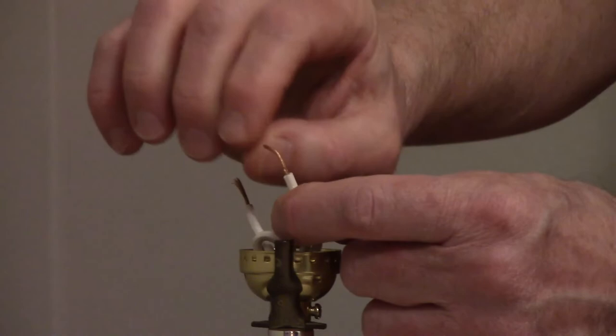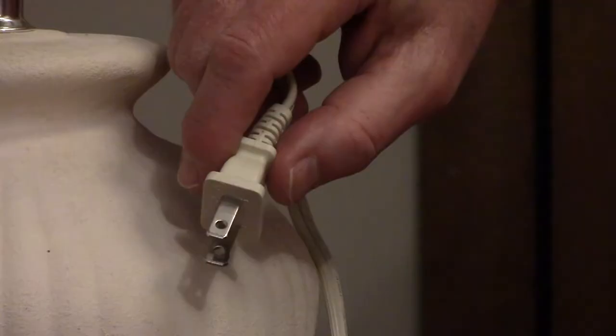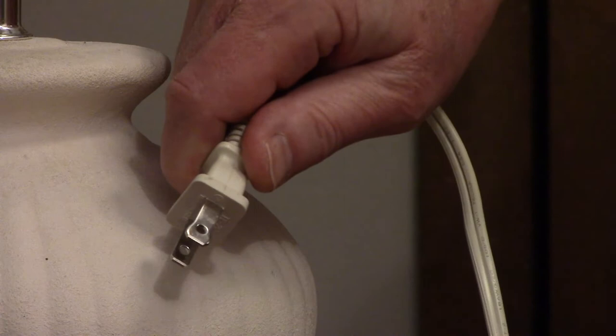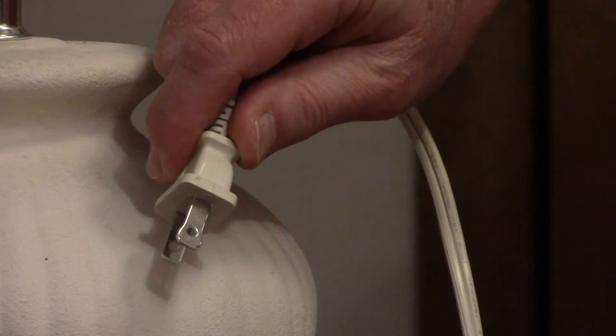On a polarized lamp plug, you have one blade that's narrow and one blade that's wide. The narrow blade is the hot wire. The wide blade is the neutral wire. The insulation on the side with the hot wire is smooth, and the insulation is ribbed on the wire that's neutral.